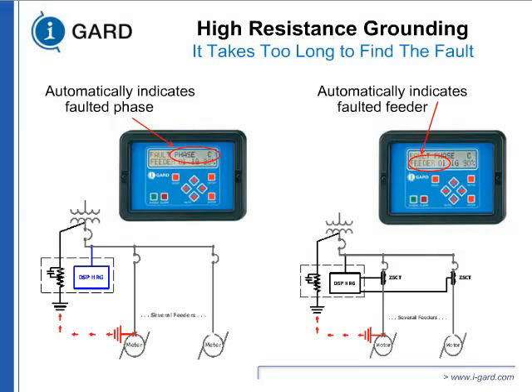Of course, if your process is very critical, you may have monitors on individual motor control centers. When we do our safety systems, we will have a ground fault monitor on every piece of equipment that can affect the safety system. It tells us exactly which one it is, so we'll have a backup. So you can see industry has responded to needs, whichever way you need. That is an excellent system for you to save time if you don't have time to detect or don't have manpower.